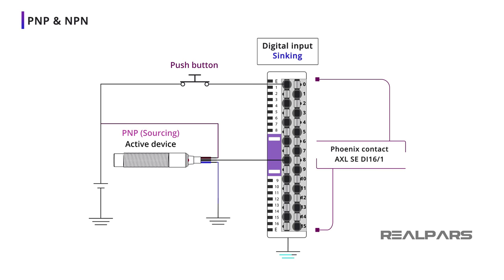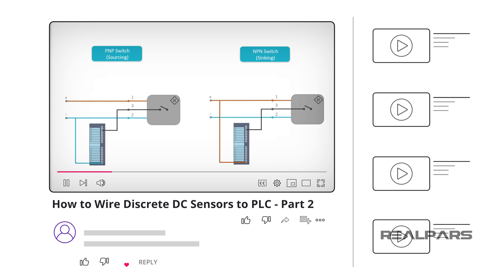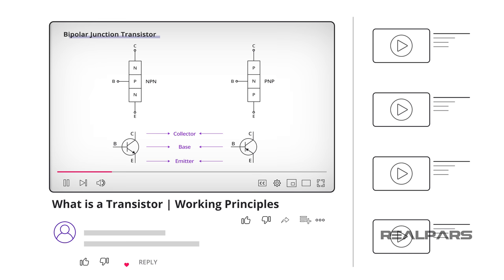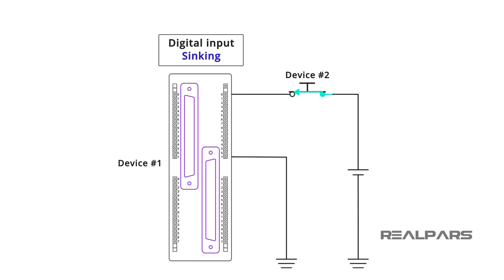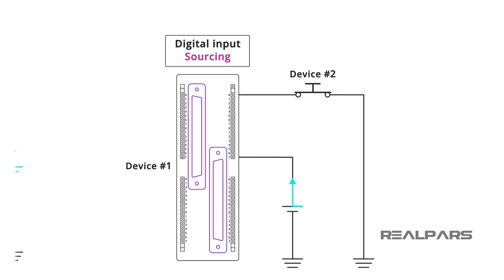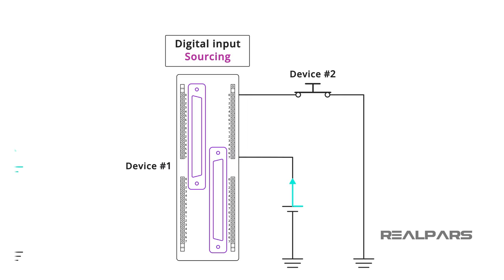If you want to learn more, you might want to review two of our other videos called 'How to Wire Discrete DC Sensors to PLC Part 2' and 'What is a Transistor Working Principles.' You can find the links in the description. Let's review what we've covered: a digital input module detects one of the two possible conditions of an input device — open or closed. Digital input modules detect either a no-voltage or voltage condition at the input. A sinking input module will have the current flowing into it; a sourcing input module will have the current flowing out of it. PLC vendors offer both sinking and sourcing digital input modules. An NPN device is a sinking device, and a PNP device is a sourcing device.